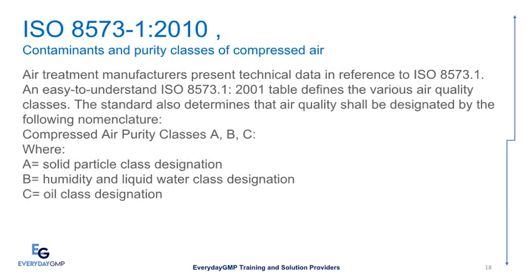Air treatment manufacturers present technical data in reference to ISO 8573.1. An easy-to-understand ISO 8573-1-2010 table defines the various air quality classes. The standard also determines that air quality shall be designated by the following nomenclature: Compressed air purity classes A, B, C — where A equals solid particle class designation, B equals humidity and liquid water class designation, and C equals oil class designation.